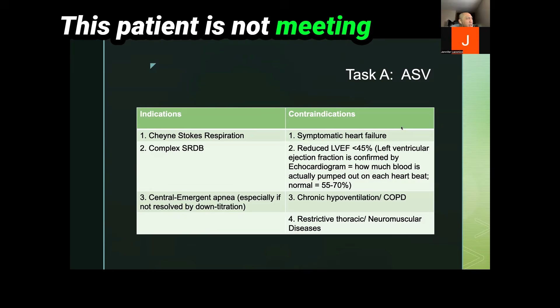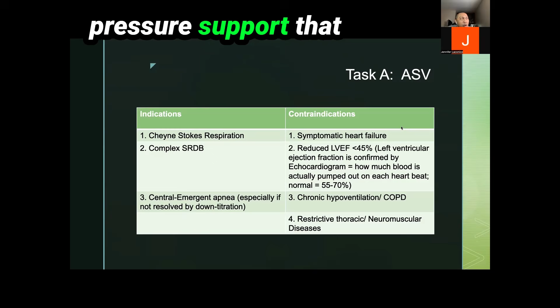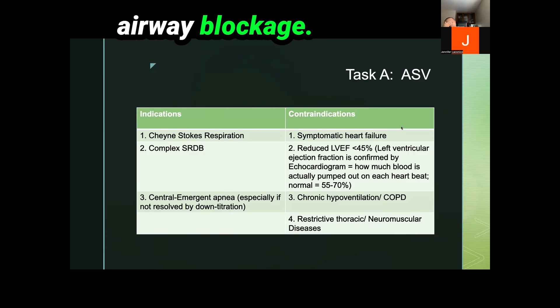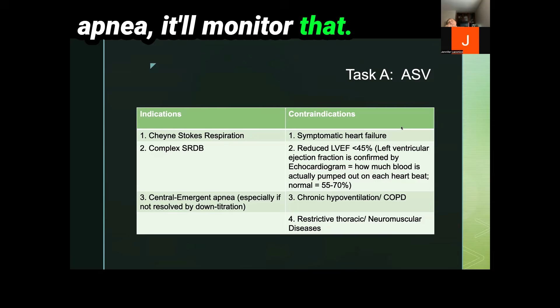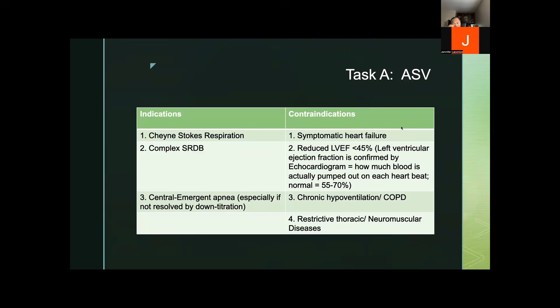It will monitor now, oh, wait a minute, this patient is not meeting their minute ventilation. I will need to support this patient by increasing my pressure support. The auto ASV is not just the minimum pressure support that it will increase. It will also increase EPAP on its own, yes. But the EPAP, typically, it monitors the upper airway blockage, whether it's snoring, flow limitation, or obstructive apnea. It will monitor that. Okay, so it's very sensitive. Okay po. Okay, good.